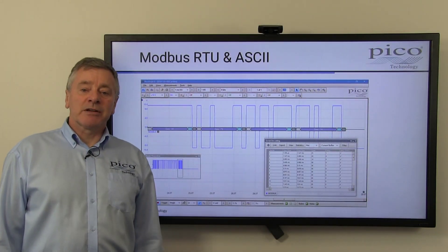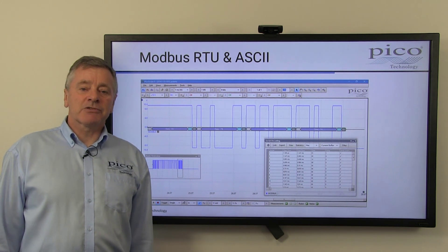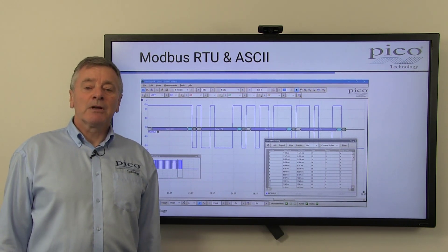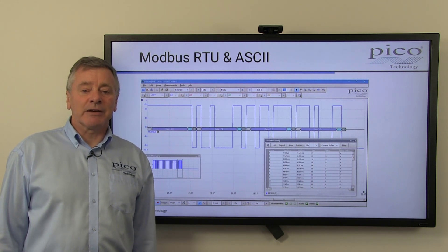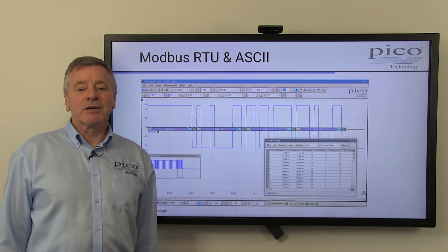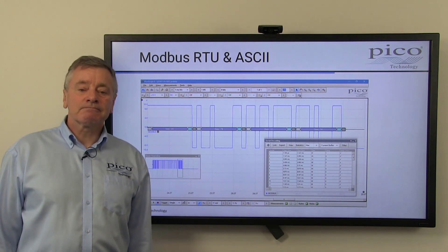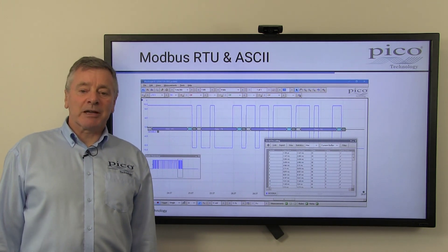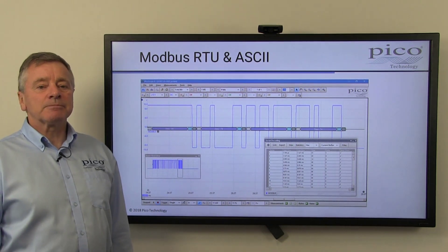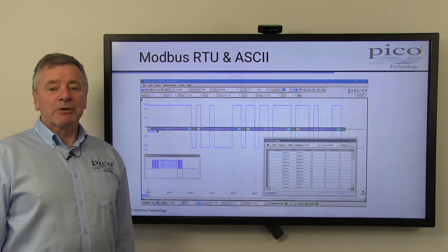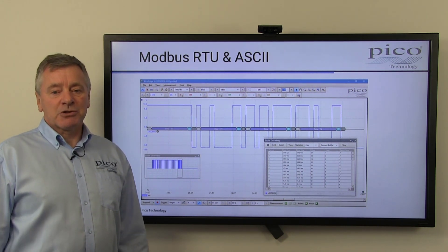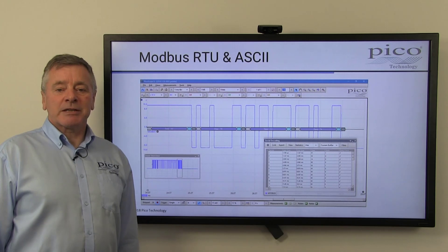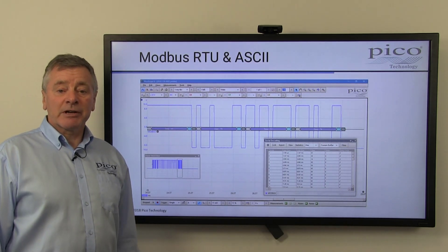MODBUS is a low-speed serial data protocol commonly used in industrial applications where a supervisory computer controls or monitors multiple remote devices. MODBUS RTU, typically for use over RS-232 single-ended or RS-485 differential lines, uses binary coding and CRC error checking. MODBUS ASCII uses ASCII characters instead of binary, making it more readable but less efficient, and it uses less effective LRC error checking. When errors occur, troubleshooting with a Picoscope using MODBUS protocol decoding allows you to correlate decoded frames with the data captured by the oscilloscope. This helps to identify where data is corrupted due to noise, interference, or incorrect voltage levels.